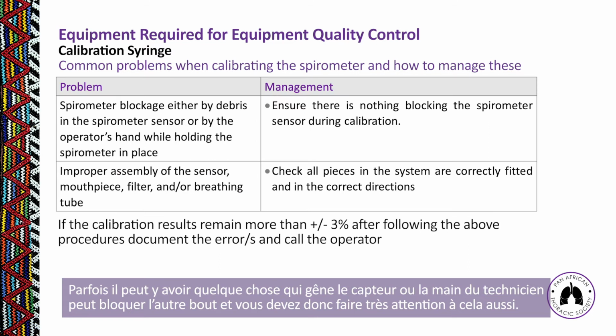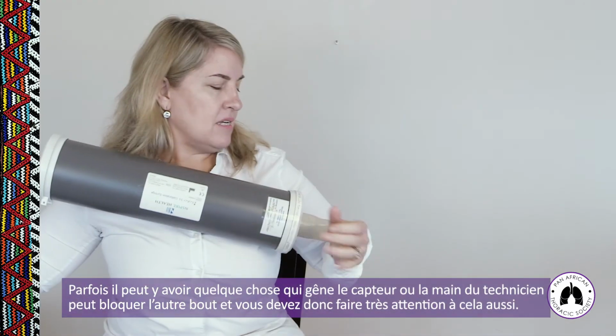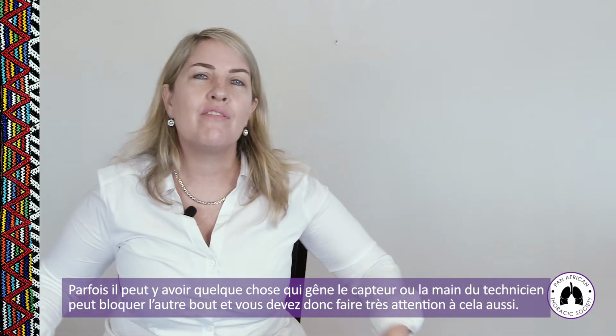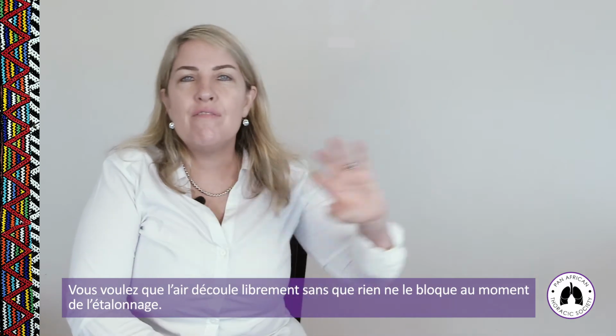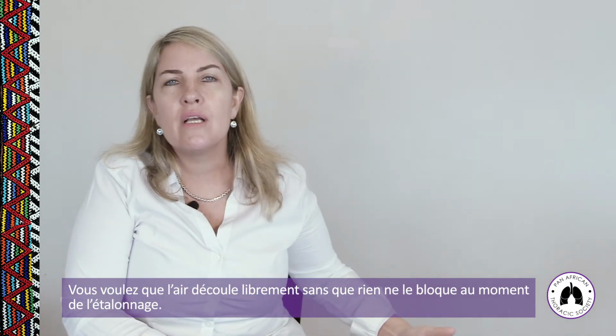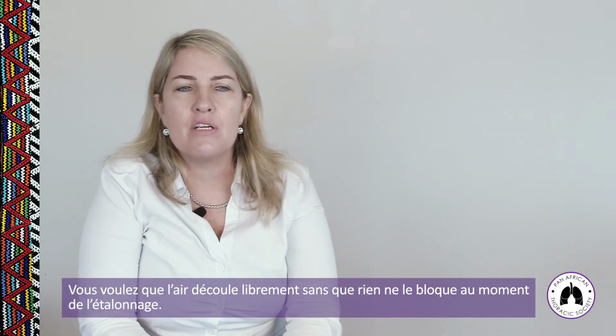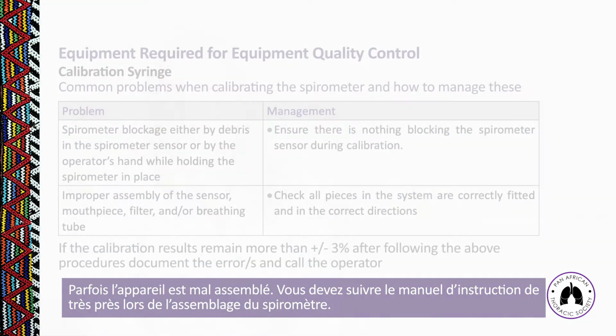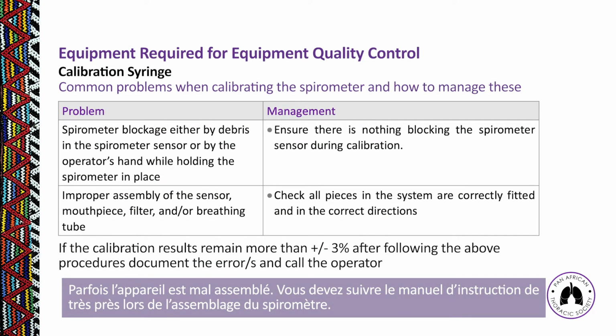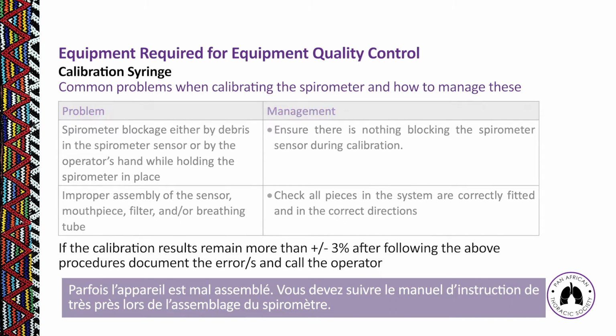Sometimes the spirometer is blocked by debris, so the spirometer sensor, or the operator's hand, can be in front of it at the time of calibration, and just be very careful of that as well. You want free-flowing air, so nothing should be occluding it when you're actually doing the calibration itself. Sometimes people assemble the equipment incorrectly, so check your manual very carefully for how your spirometer equipment needs to be assembled.